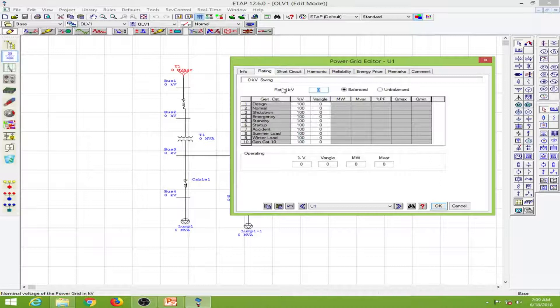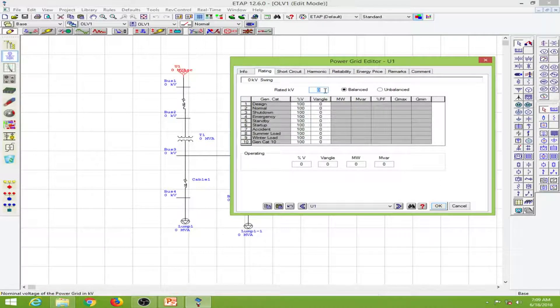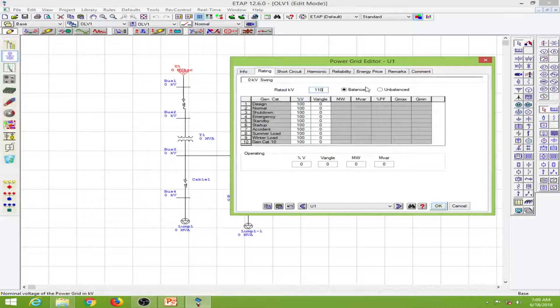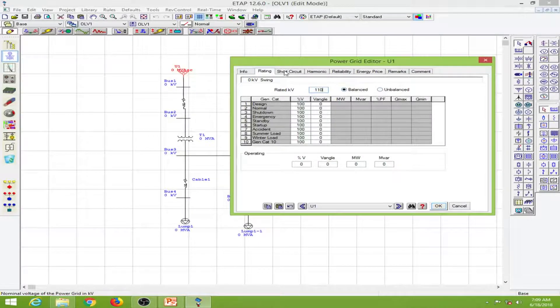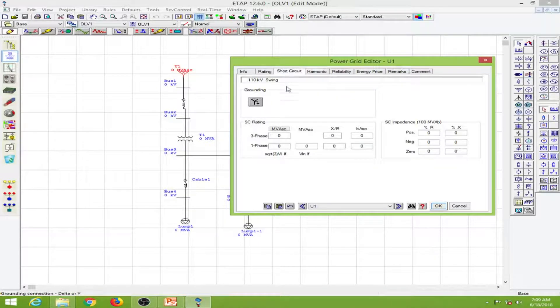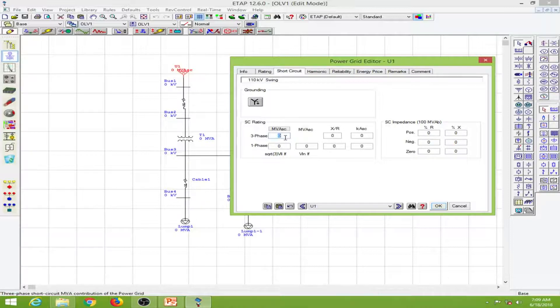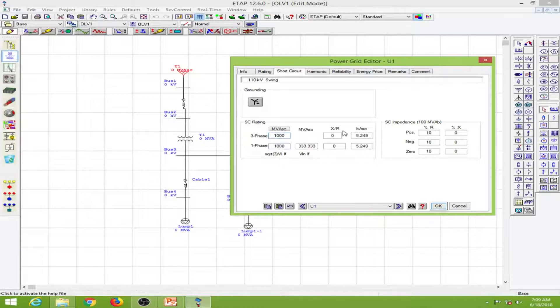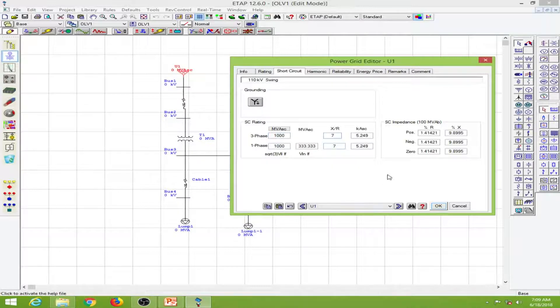We go to the rating. This power grid will be rated for 110 kV and this will be a balanced supply. I'll go to the short circuit and provide a three-phase MVA level of 1000 and the X/R ratio to be 7.